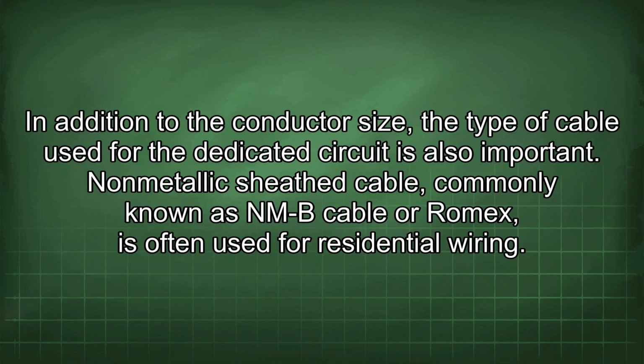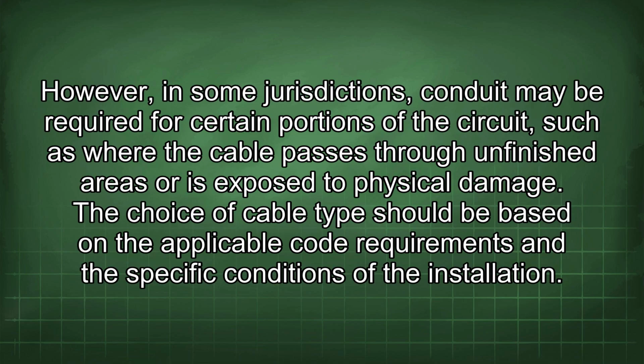In addition to the conductor size, the type of cable used for the dedicated circuit is also important. Non-metallic sheath cable, commonly known as NM-B cable or Romex, is often used for residential wiring. However, in some jurisdictions, conduit may be required for certain portions of the circuit, such as where the cable passes through unfinished areas or is exposed to physical damage.